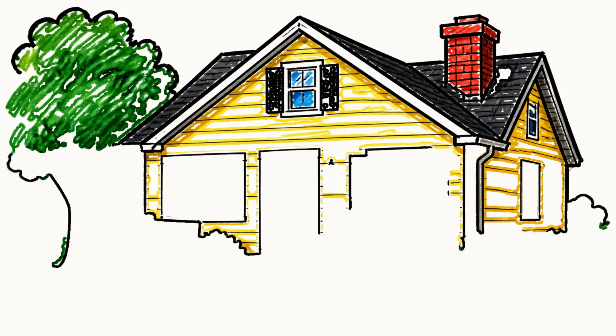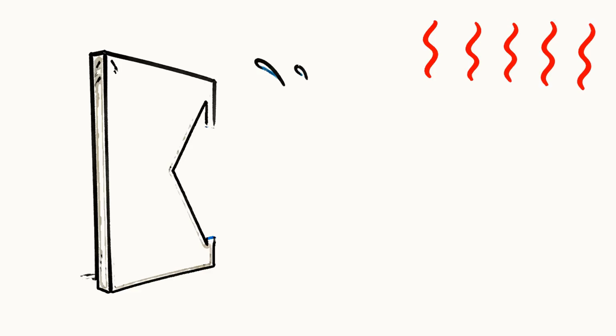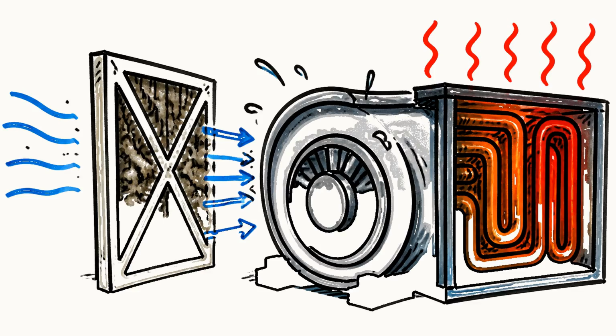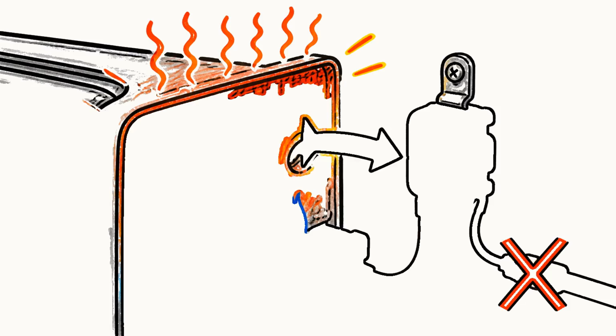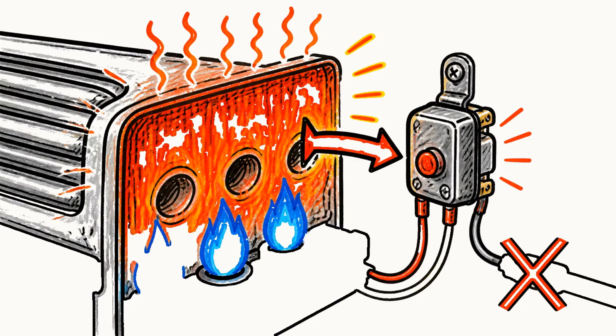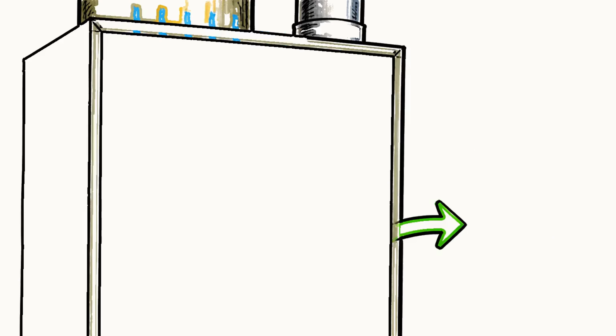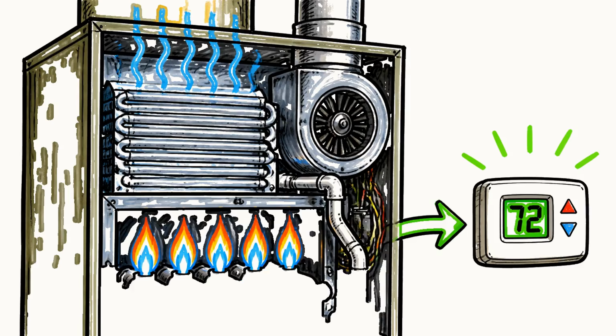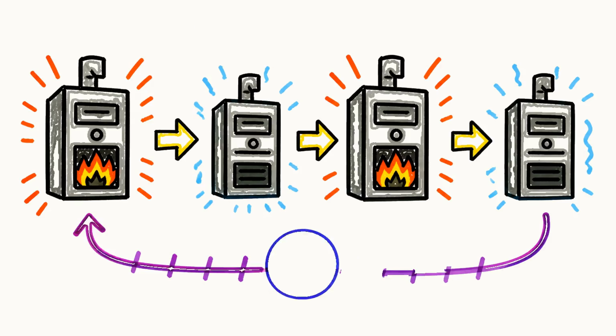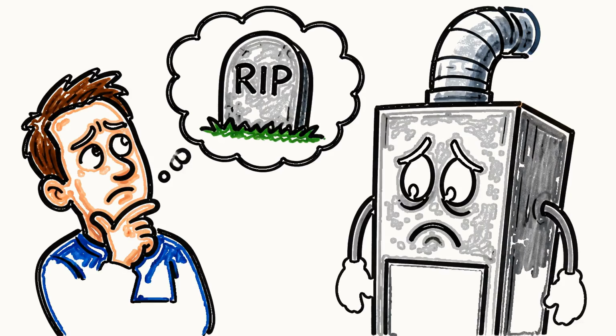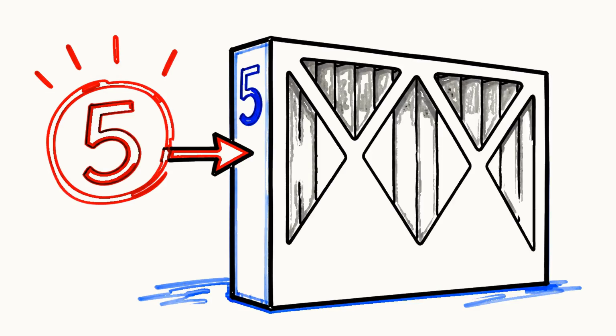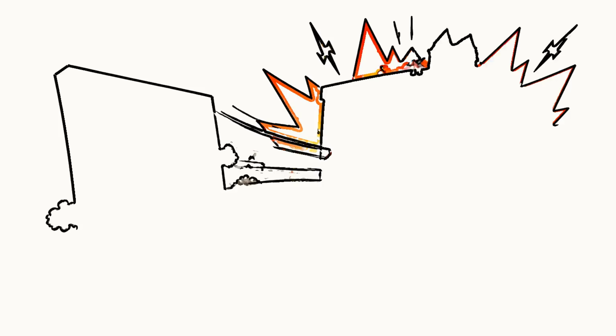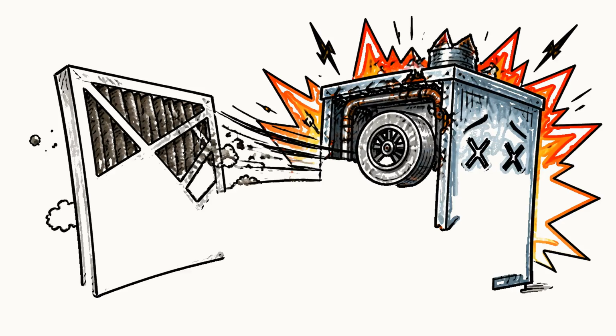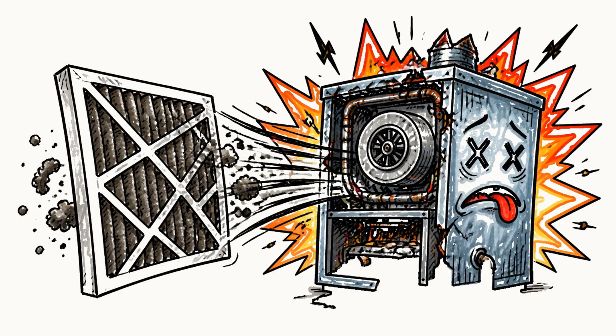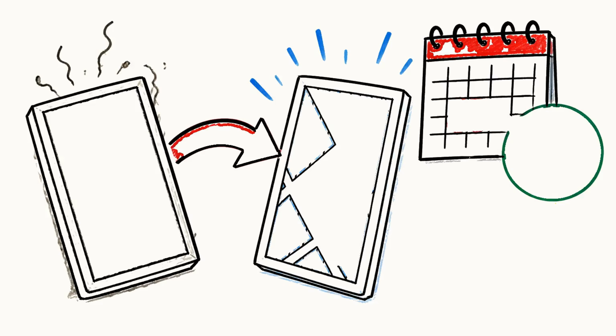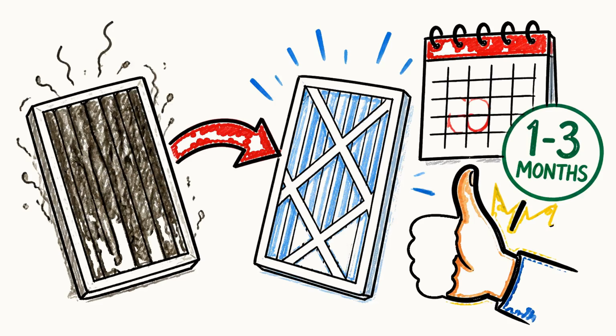Picture a house where nobody has touched the air filter since spring. It clogs up and now the blower cannot pull enough air across that hot metal. The heat exchanger overheats, a safety part called the limit switch trips and shuts the burners off. The metal cools, the burners relight, and the furnace ends up turning on and off every few minutes all night long. People hear that and assume the furnace is dying. Usually it is a $5 filter that nobody changed. A neglected filter wrecks more furnaces than almost any mechanical fault, which is a frustrating thing to learn after the fact. Swap the filter every 1 to 3 months and you have done the single most valuable thing an owner can do.